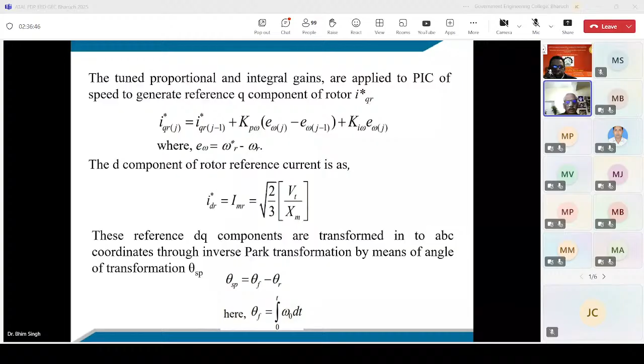If you give the reactive power to the induction machine on the stator side, you have to give the full amount corresponding to 50 hertz, maybe 60% of the rating normally, since the power factor of the induction machine is around 0.8. It means you have a reactive power of 60% from the stator side. But from the rotor side, this goes as slip times. The slip is not more than 0.3, so the reactive power given from the rotor side is hardly 30%, or even much lower than that.